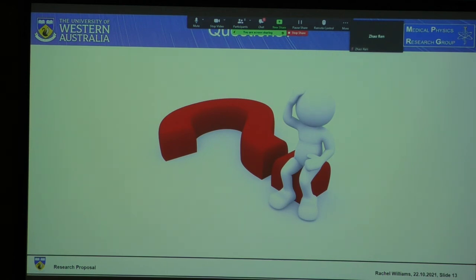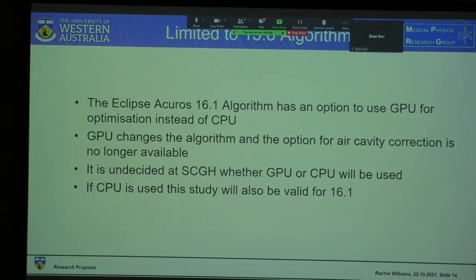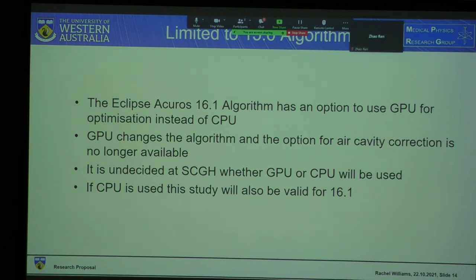Question: You mentioned an update to the algorithm is upcoming — do you know what's actually changing in that update? Response: Yes. The 16.1 algorithm has an option to use GPU for optimisation instead of CPU. GPU changes the algorithm and the option for air cavity correction is no longer available. It's not yet decided at Charlie's whether GPU or CPU will be used. If CPU is used, the study is also valid for 16.1, but if not, it isn't.